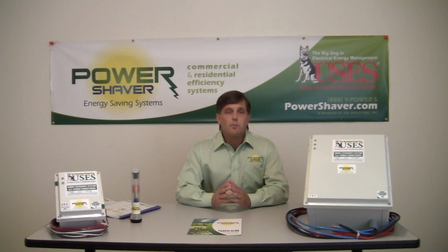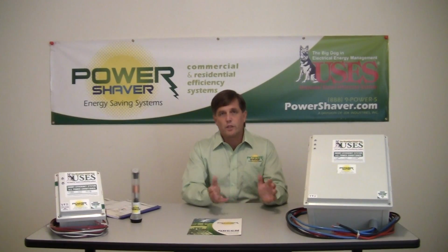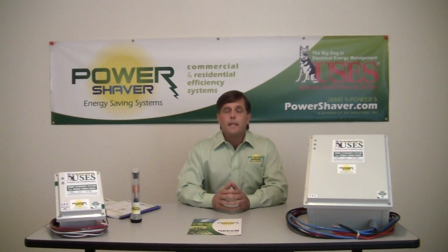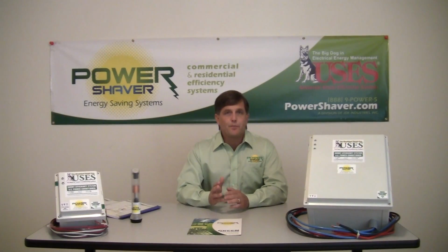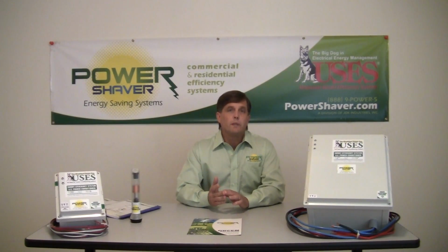Next, we incorporate harmonic filtering, which is in the lower order harmful harmonic in the system. This is non-power waveform distorting current. It occupies space. It causes in your distribution system poor power quality interruptions. But as of late, the most beneficial reason for reducing harmonics is to reduce the billed kWh. Because of the utility company's multiplier billing system, reducing total current, non-power current, real power current, and the aforementioned VAR, volt amp reactance, reduces the billed kWh through what's called a default power factor billing penalty.